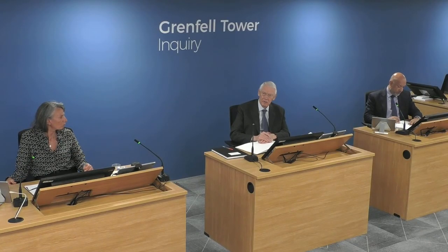I see. Can I just check that I've understood this? I think what you're saying is that if you, Mr. Marney or anyone else come to that, designing a system, you would design it to criteria which included 2 metres a second inflow through the stair door with no other doors open, that giving you a certain flow rate to achieve. But you might at the same time be aware that with a flat door open and a window open to the outside, the flow rate would not be as high as 2 metres. But you would regard that as acceptable? I think that's what you'd have to presume, yeah.